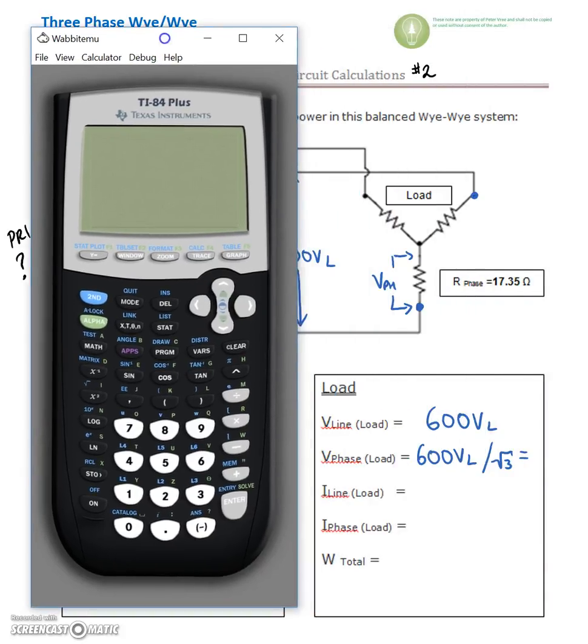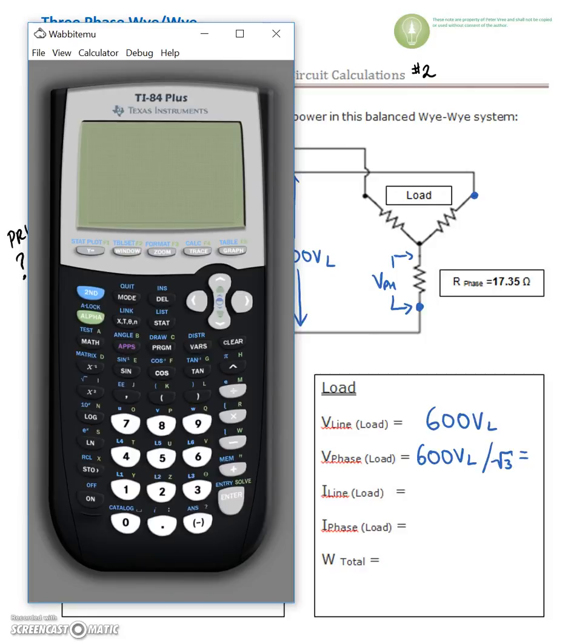Let's just bring this across. So we've got 600 volts divided by the square root of 3, or 1.732, and that gives us 346.4. I'm going to go with standard voltages, so I'm going to round that up to 347 volts.